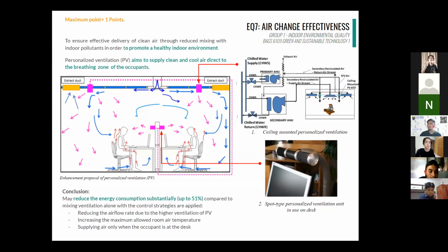While the spot type is more concerned with the furniture layout, which needs to stay constant at the workspace. But both of these PV types have been concluded to reduce the energy consumption substantially, up to 51% compared to a mixing ventilator alone, with the control strategy applied, which reduces the airflow rate, increases the maximum allowed room temperature, and supplies air only to the occupants at the desks. Okay, that's all. Next.